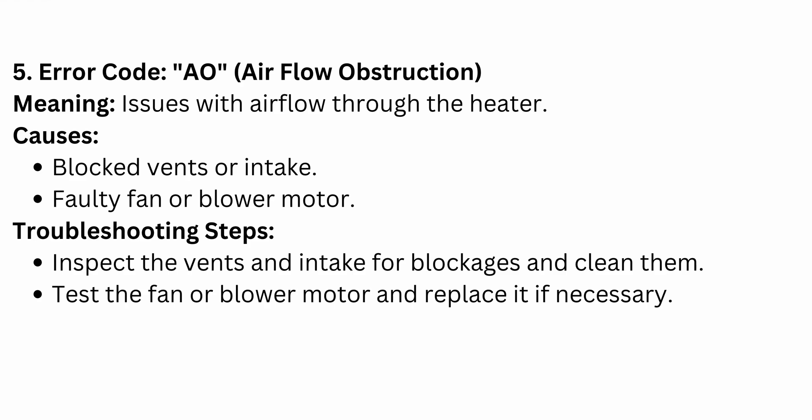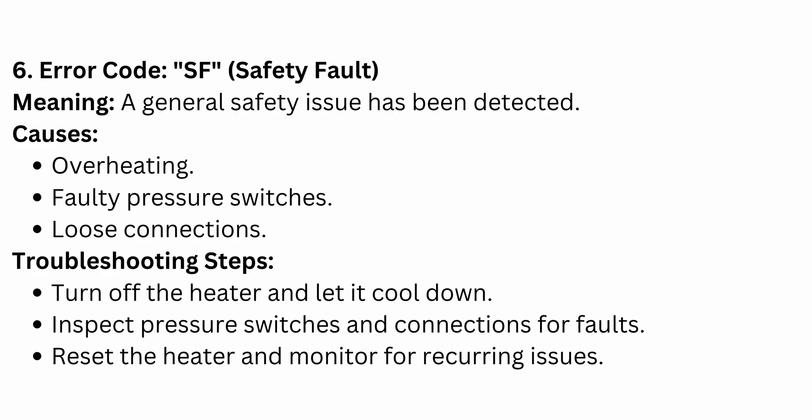Simply replace any defective part you find during this process and make sure there is no blockage or dirt and debris accumulated on your heater. Another code is SF — Safety Fault — a general safety issue has been detected. Causes can be overheating due to low water supply, faulty pressure switches, or loose connections. Turn off the heater and let it cool down, inspect pressure switches and connections for faults, reset the heater, and monitor for recurring issues. You can even turn it off for a few hours so it can restart on its own.